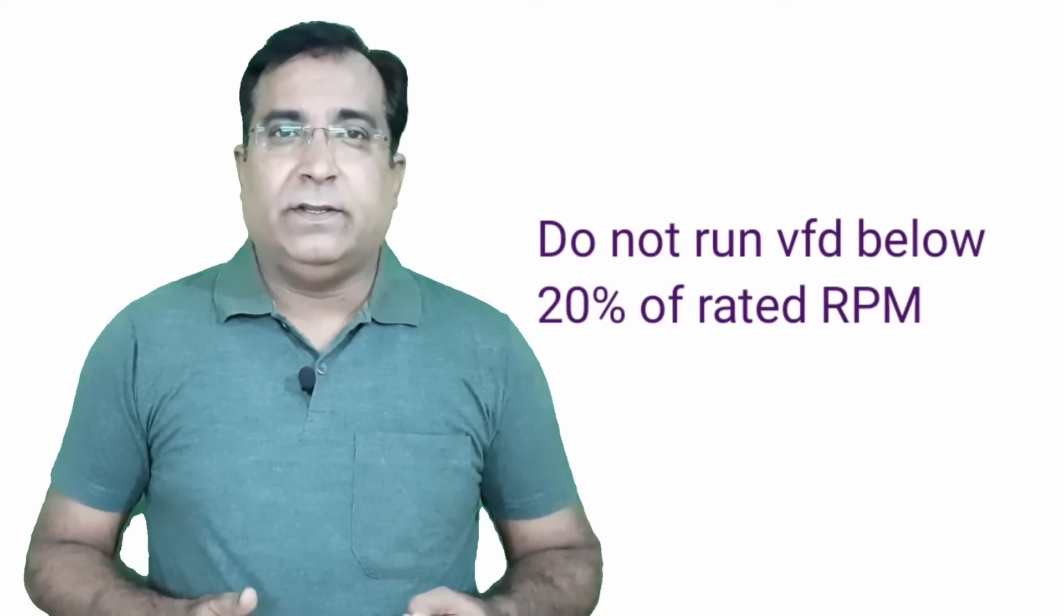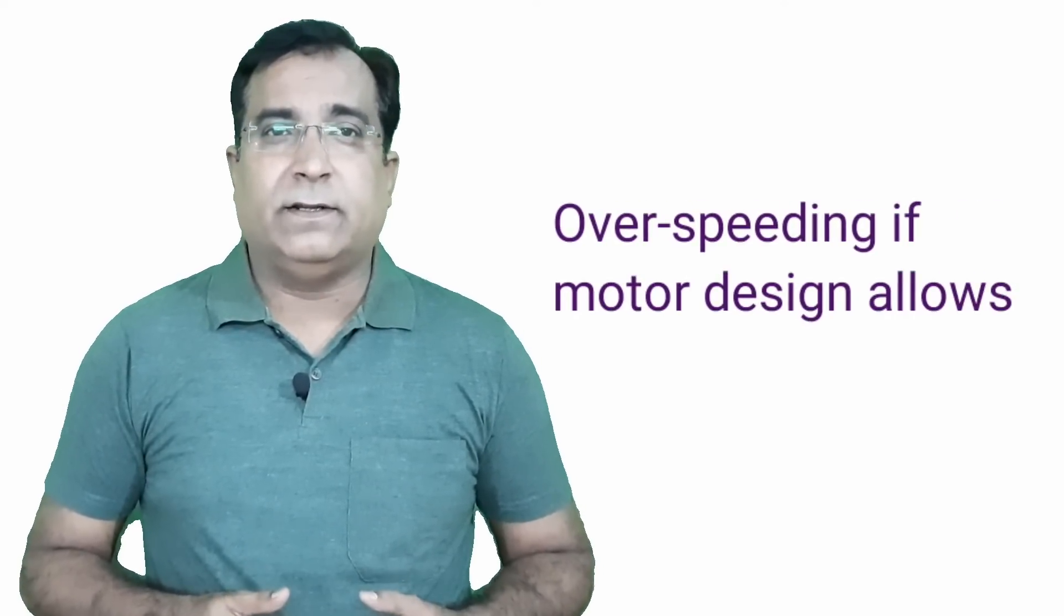Speed range. The motor should never run below 20% of rated speed. There will be issue of motor cooling. If you have to run below 20% speed, then you will have to arrange for auxiliary motor cooling system. The same is true when you are going to run motor at speed higher than rated. Confirm if motor design allows it.